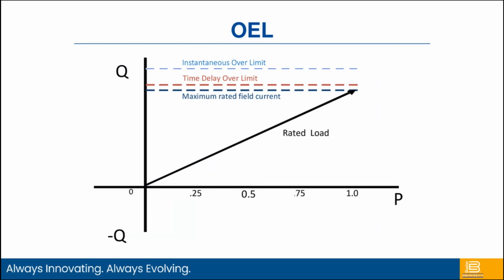Over excitation is looking at field output, so we're looking at field current. This is to make sure the machine's not getting overexcited. We have two different types within the device: a summing point type and a takeover type limiter. Takeover type is more of an inverse type limiter, whereas with a summing point we're setting fixed delays. This particular diagram shows a summing point over excitation limiter, where I have an instantaneous over limit. I want to set a cap on how much current I'm going to allow the DECS to output, and it's going to cap it at an instantaneous limit.